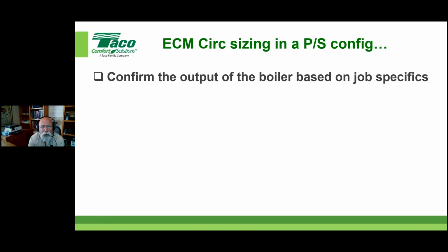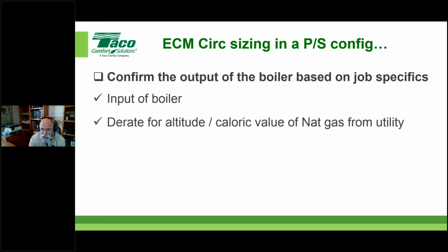Confirm what the output of the boiler is based on the job specifics. We need to know what the input is, and whether there's any derate for altitude, caloric value, or anything like that. A lot of times the natural gas utility will tell you their caloric value, which is how many BTUs a cubic foot of gas can produce at that given altitude. That's typically more accurate, because it comes from the people selling you the gas and putting the recipe together.